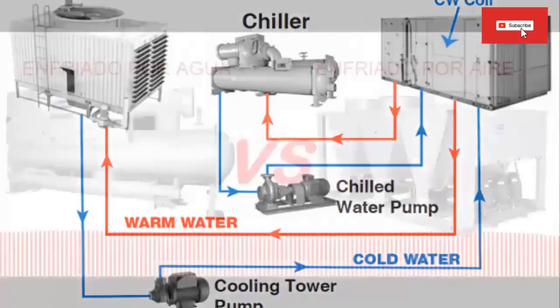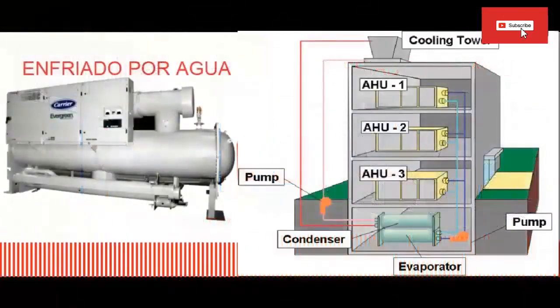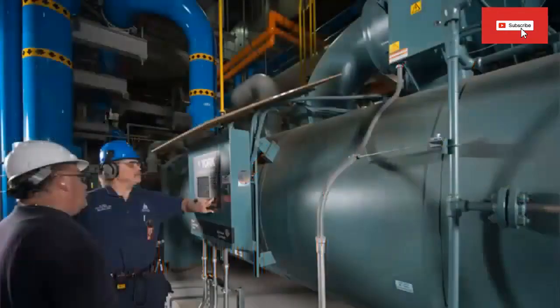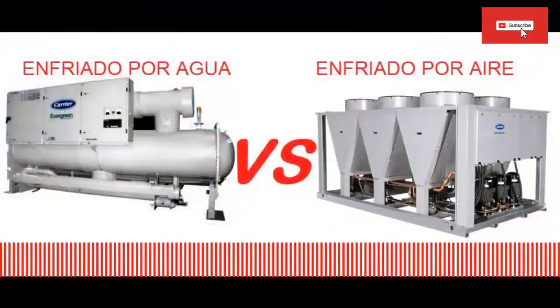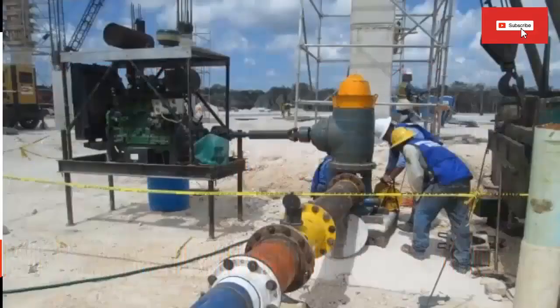3. If the location of the chiller is a closed basement, we should lean towards a water-cooled chiller. 4. The water-cooled chiller needs a constant handyman. This is due to working with the fresh water circuit that is open to the outside environment, in the cooling towers. 5. The water-cooled chiller requires a constant and reliable water resource at all times of the year. 6. Water-cooled chiller has a longer shelf life, especially in compressors.